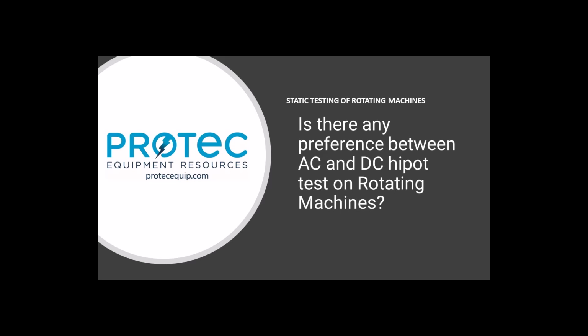And unlike cables, like if you attended last month, Matt, to the medium voltage cable, in the cable world, particularly with extruded dielectric cables, cross-linked polyethylene, or ethylene propylene rubber, the way this material ages over time and creates this phenomenon called water treeing, testing with direct high voltage direct current has been really kind of faded out of the industry because it actually causes accelerated growth of these fault channels. That is not the issue with motors and the tape insulators that are being used, the mica, the porcelain, the glass, and more of a laminated type of insulating system. So DC is still very strong in testing of the rotating machines.